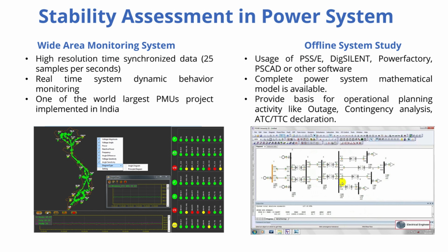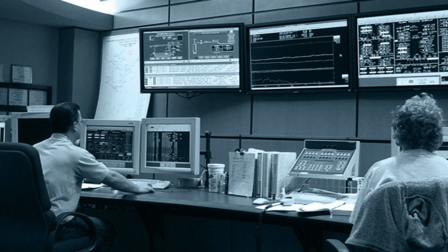It really gives you an appreciation for the sheer complexity involved in keeping our power grid reliable. It really does. The presentation shows stability isn't just one thing. It's this multi-layered challenge, balancing physics across different timescales, from millisecond transients to minute-long voltage issues. It's a constant dynamic dance. And adding all these new inverter-based technologies just adds more layers, new types of interactions to worry about. It's amazing how interconnected it all is, too. A fault triggers a swing, which causes voltage dips, which might excite an oscillation. Exactly. One problem can easily cascade into others.